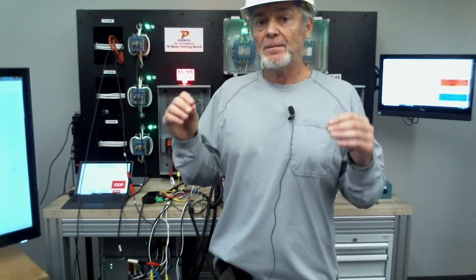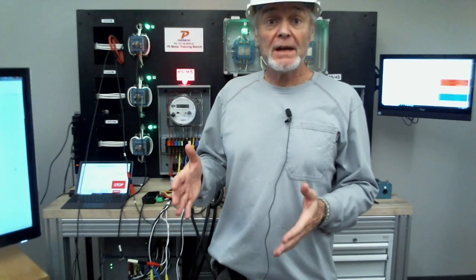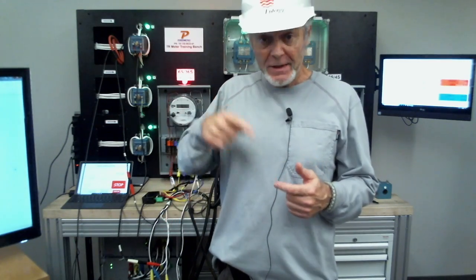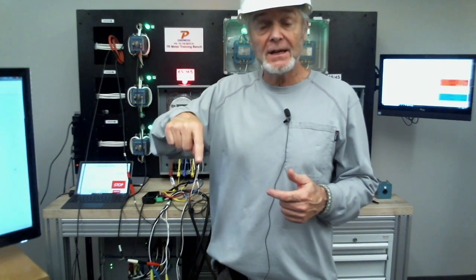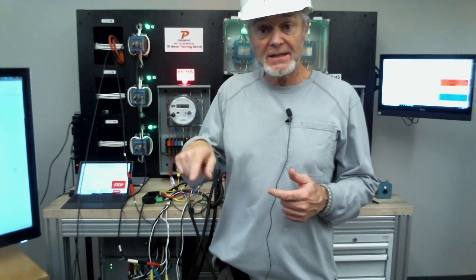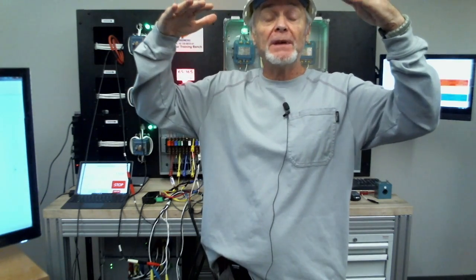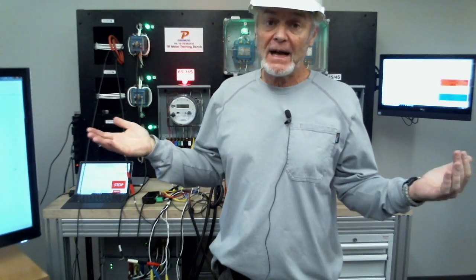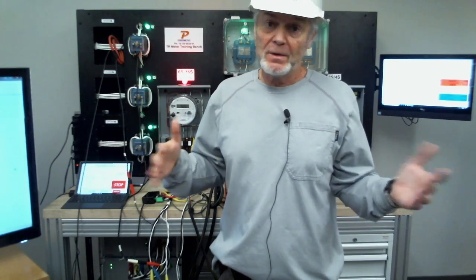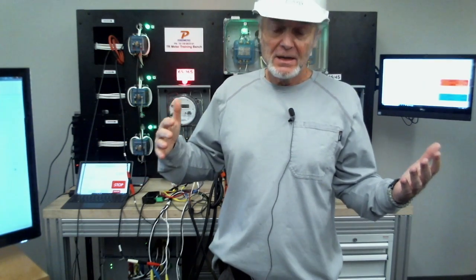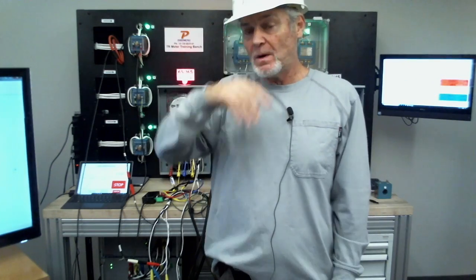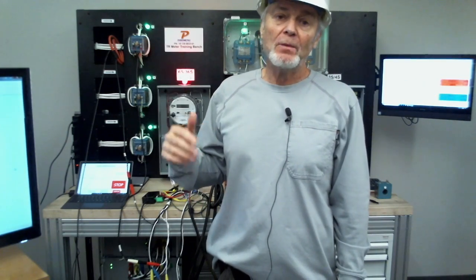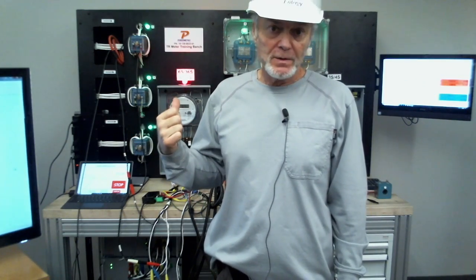So we have the load boost capability, which you can use out there in the field. We can use a drive cable to drive current through the CT, and when we drive that current through the CT, now we're bringing it up to where it needs to be for a legit test. So we show up out there, and it's a 205 with like 2 amps on it. Well, we know that's not going to work. I need to have more than that. So that's what we're looking for, and we can do that with the load boost test.